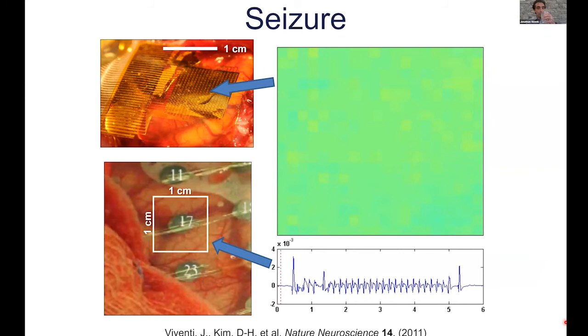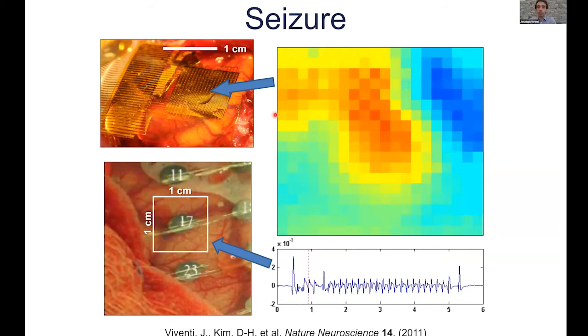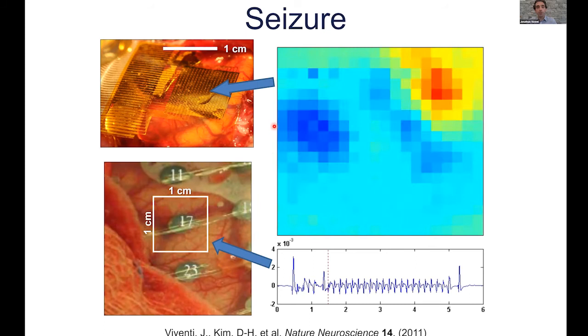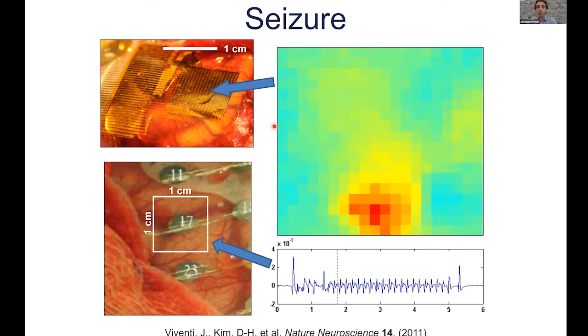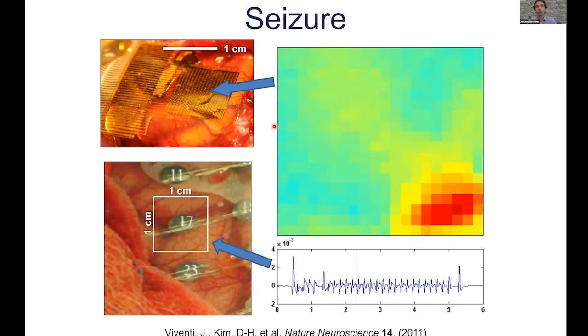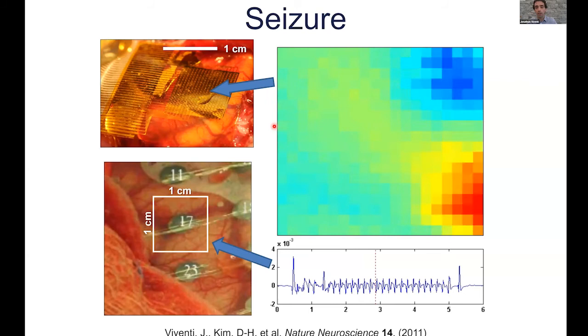These techniques, really common in CMOS digital cameras and image sensors, we've applied to making a kind of image sensor for the brain. In one square centimeter of brain, rather than one single electrode waveform from clinical tools, we now have 360 electrodes showing raw voltage slowed down 18 times during an induced seizure. We observed complicated spatial dynamics and repetitive spatial patterns occurring on the micro scale over and over again, inspiring us to ask whether we could better prevent and stop seizures if we could map the spatial dynamics of these events.